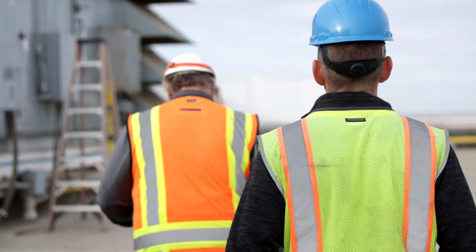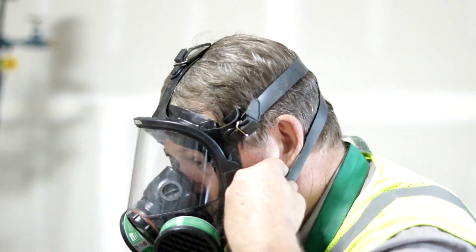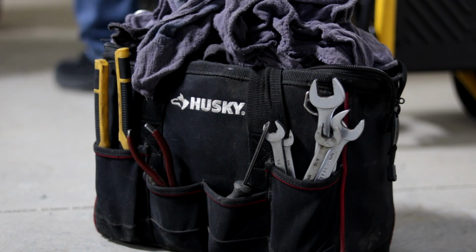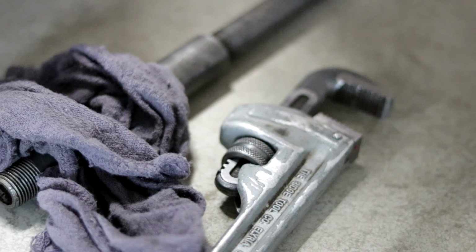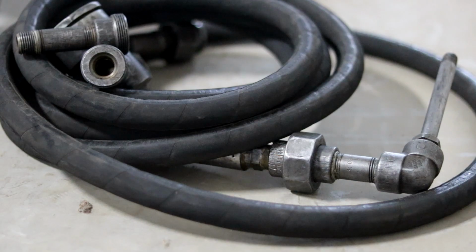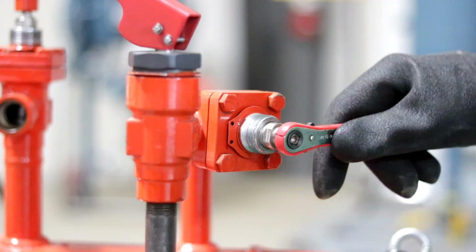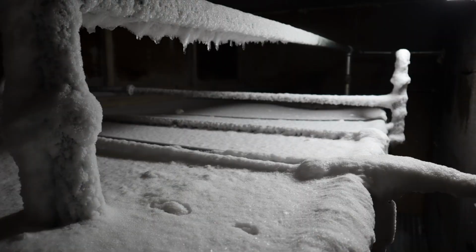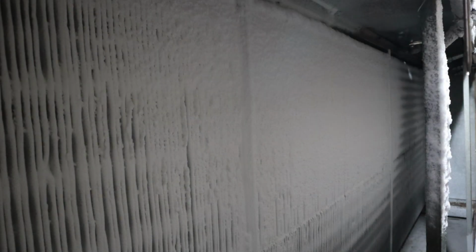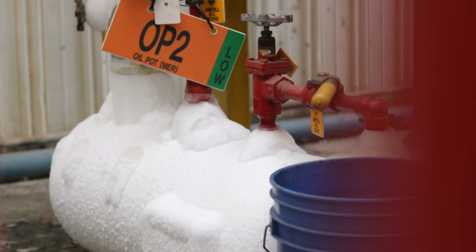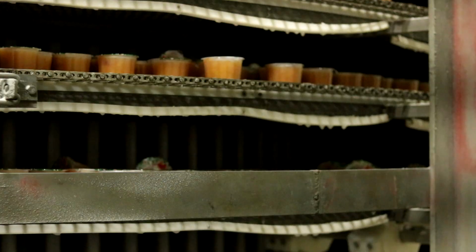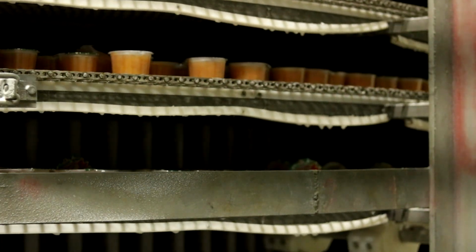Non-condensable gases are mainly introduced in two ways. First, when performing maintenance, equipment is open to atmospheric conditions. If the equipment is not evacuated before placing it back into service, the air in the equipment will become trapped in the system as a non-condensable gas. Second, systems that require low temperatures operate at vacuum pressures. This means that if there is a leak, rather than refrigerant leaving the system, air will be sucked into it.